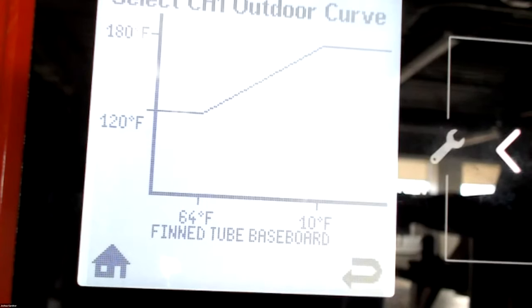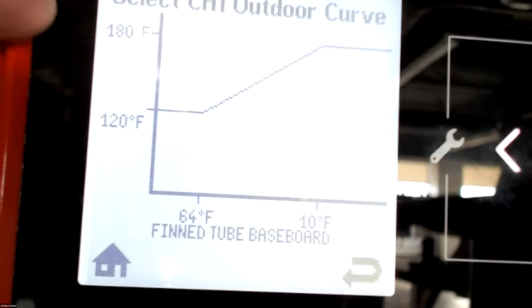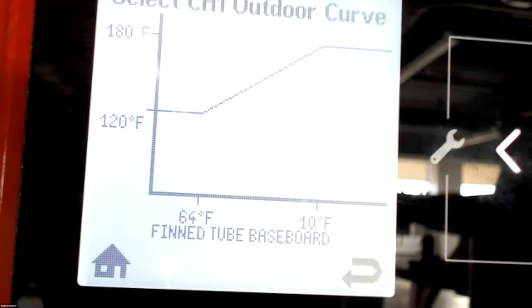On most applications, guys that use this, we find that the high is good, 180, but our low at 120, we're not heating that house effectively. And we got to bring that 120 up. So this is good as a quick setup, but again, that's why we want to go in the back end of the control, and I want to adjust this. I would go in, if I'm going into just a regular ranch, they got baseboard in there, they got a bunch of furniture, couches and beds and bureaus in front of the stuff. I'm going to leave my high temp at 180, but I'm going to take my 120 low, and I'm probably going to bump that up to like 160, maybe even 170 if there's a lot of furniture.